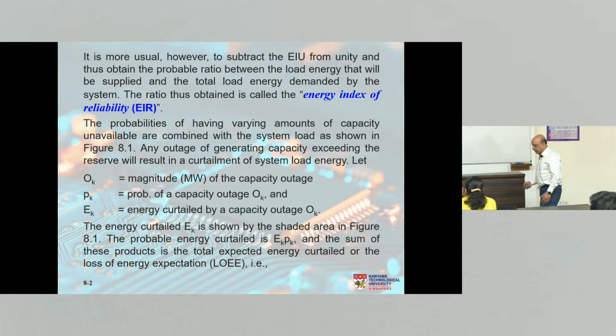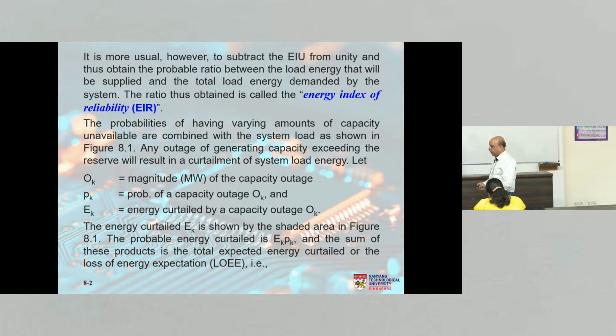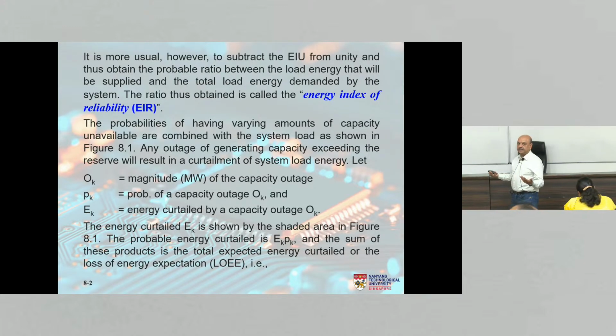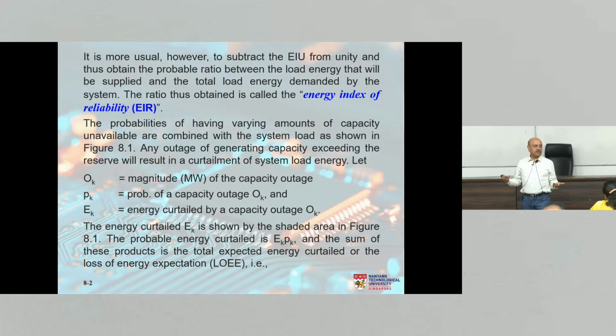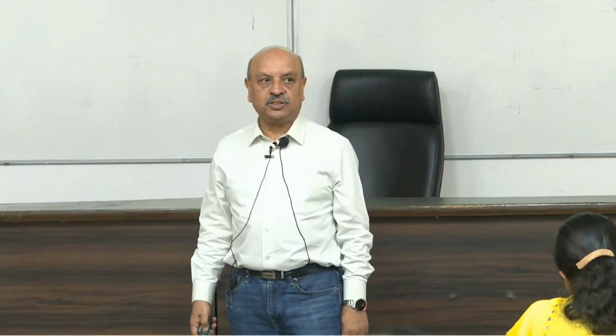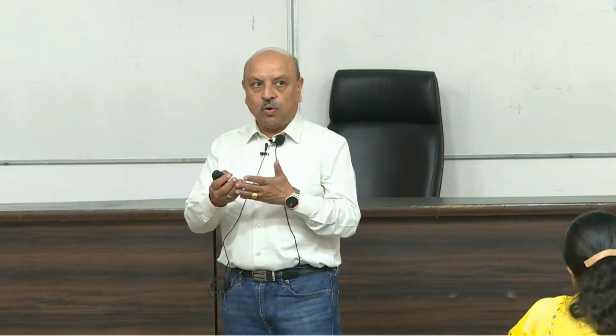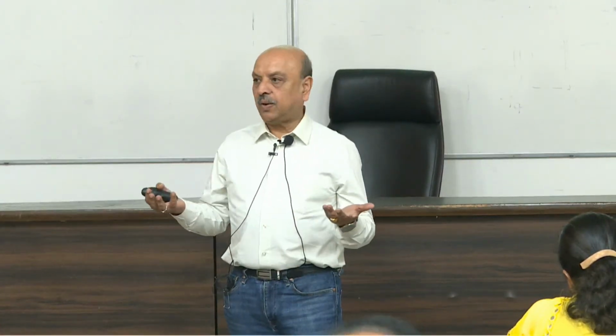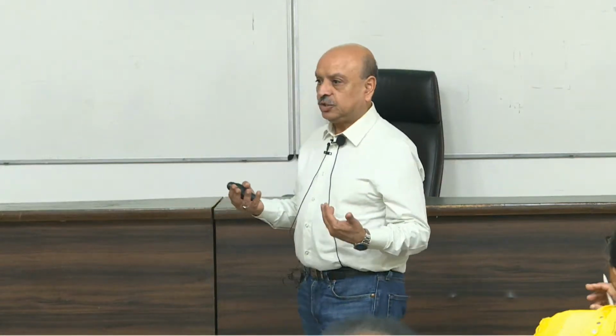Now the reason why we calculate these indices is that we want to compare two totally different systems on the same pedestal. That means they may have similar peak loads, they may have similar generation composition, but once you want to compare different configurations for the future, it is always better to compare them on a per unit basis. So that's the reason for the EIU and EIR, energy index of unreliability and reliability, to be used sometimes.